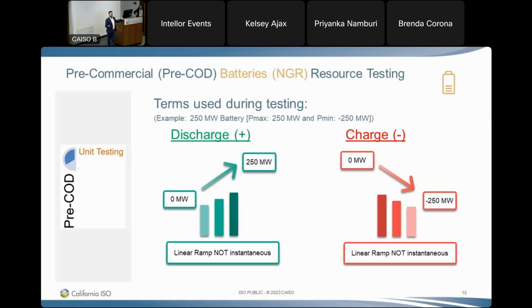One of the first batteries that we had was down in San Diego. It was a 250 megawatt battery, and I recall doing a test. I called them and said, hey, I want you to perform an unannounced test. I need you to go to 0 to 250 megawatts. We started the unannounced test, and all of a sudden, like a light switch, 0, boom, 250. I was like, whoa, what did I just see? Was this real? I called the site and said, did you really just go from 0 to 250 like a light switch, instantaneous? They said, oh yeah, we did. I said, no, you're supposed to ramp, you know how to ramp? And they said, we were never told that. It's like, no, you can't have 250 megawatts come on the system instantaneously. Just 0 to 250, that's cool, it's neat, but for reliability, you just shot our system and our frequency through the roof.